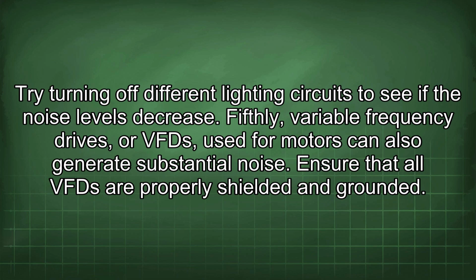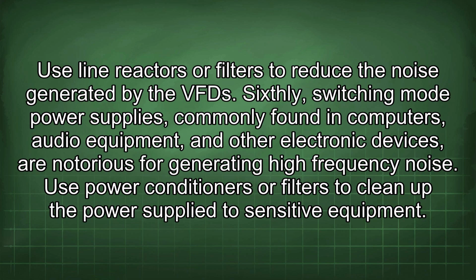Fifthly, variable frequency drives, or VFDs, used for motors can also generate substantial noise. Ensure that all VFDs are properly shielded and grounded. Use line reactors or filters to reduce the noise generated by the VFD. Sixthly, switching mode power supplies, commonly found in computers, audio equipment, and other electronic devices, are notorious for generating high-frequency noise. Use power conditioners or filters to clean the power supply to sensitive equipment.